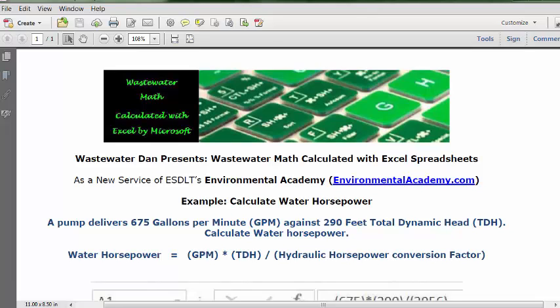Water horsepower is a calculation that requires using flow rate as gallons per minute times the total head pressure, which is TDH. Those two numbers multiplied together, divided by a standard conversion factor of hydraulic horsepower. So that's the formula.